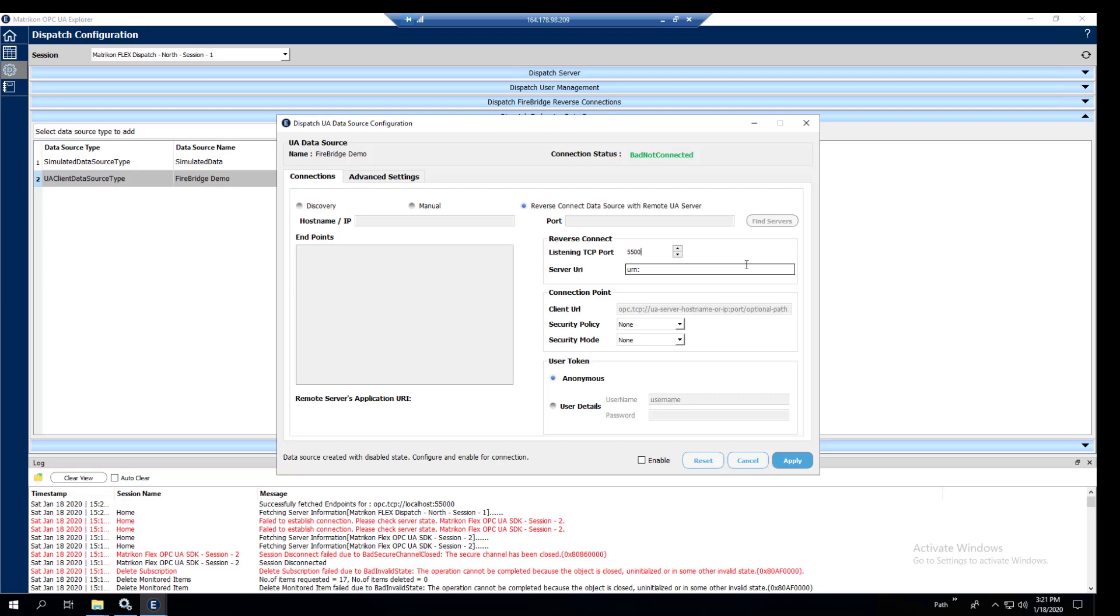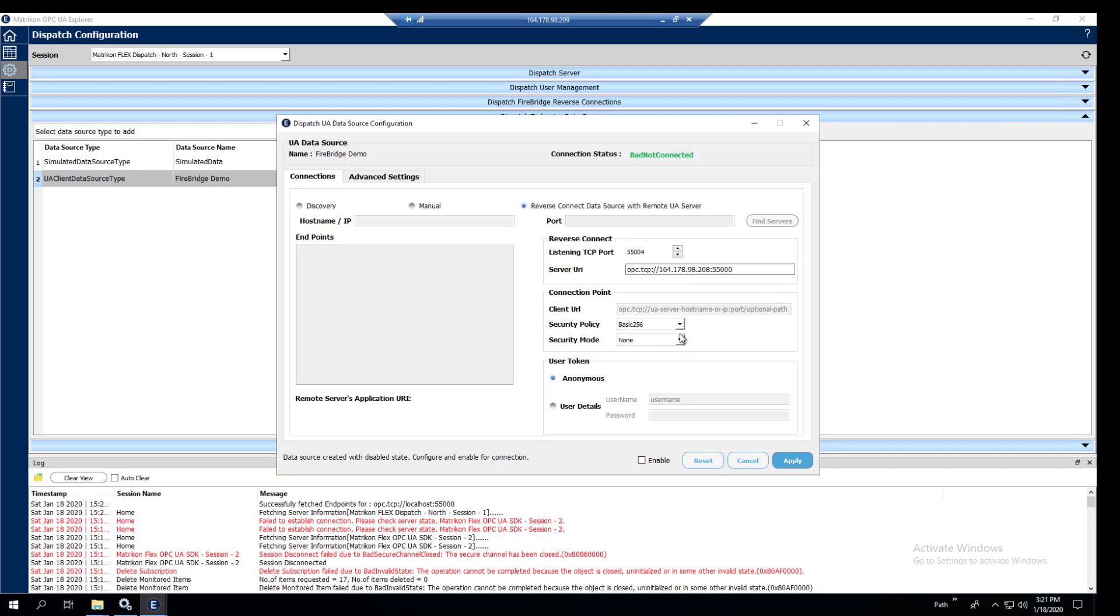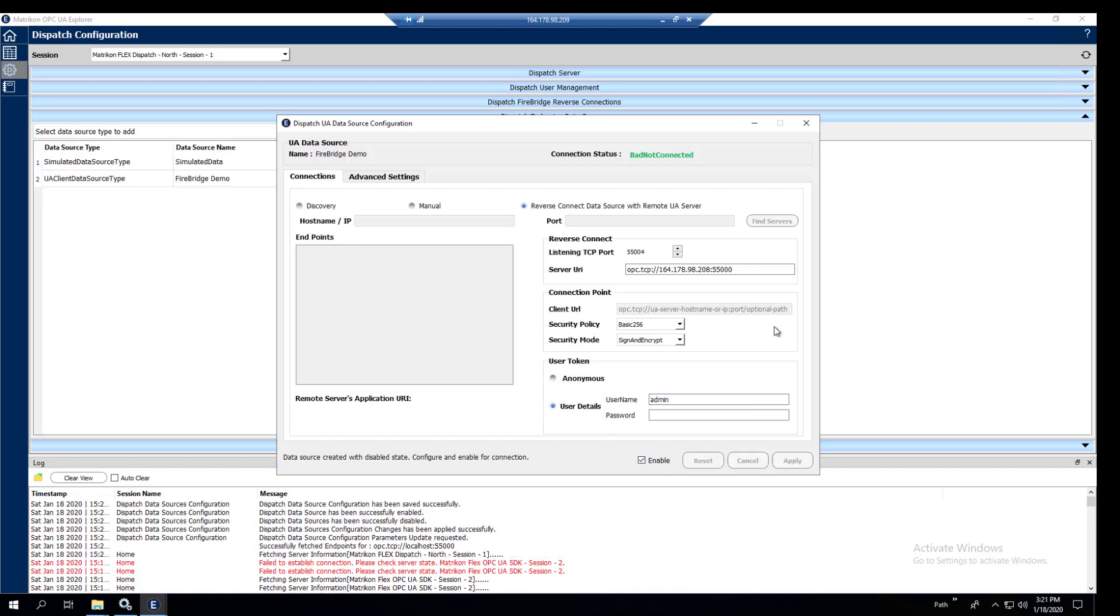The first thing we're going to do is set the listening port and that is going to be 55004. And then we're going to put the server URI in, which I'm just going to copy and paste in right now. Below we're going to set the security policy and security mode, basic256 and sign and encrypt, username. And this is what we've been using for both of these. Set it to enable and apply.